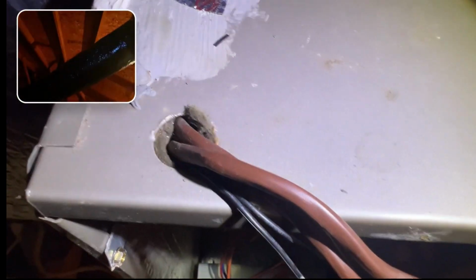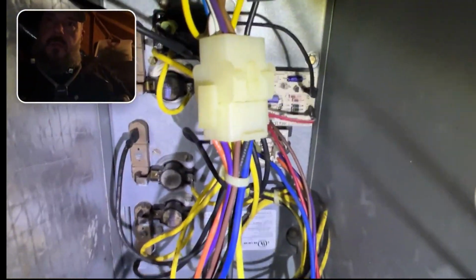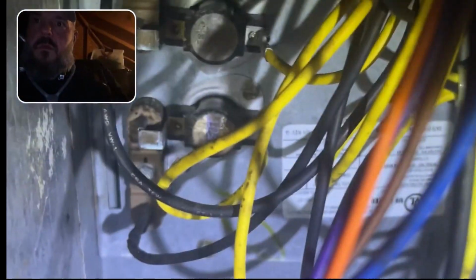However, he did nothing with the AC system itself, the air handler itself. So this air handler is a Carrier unit, it is a negative pressure unit. So we have countless entry points from the attic. This plug right here was actually cracked open. We have some electrical high voltage with no connector, no sealing whatsoever, no air sealing. We have low voltage, no connector, no air sealing. And we have some microbial growth.